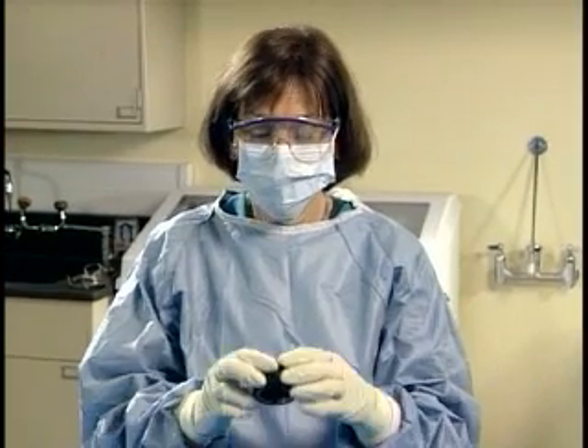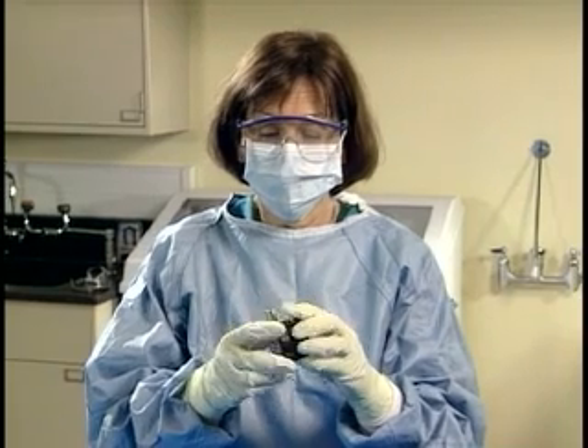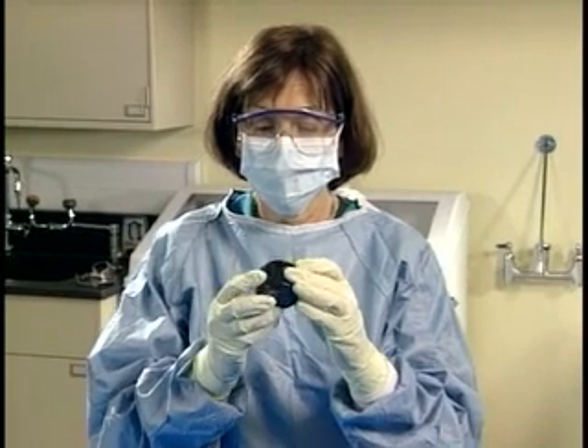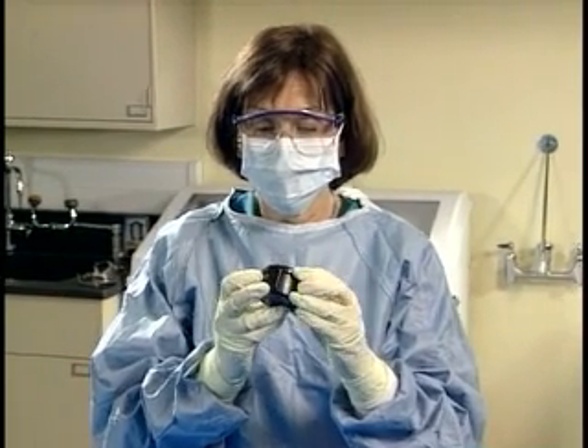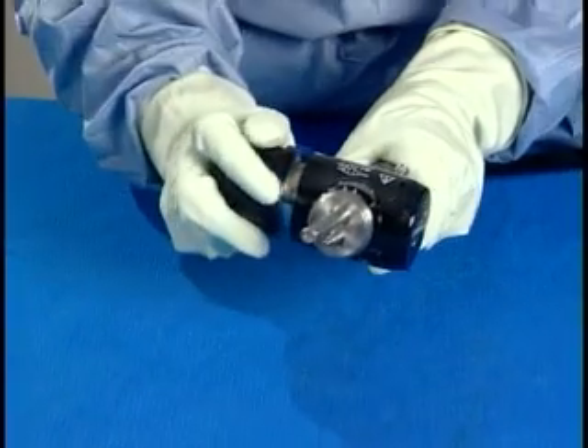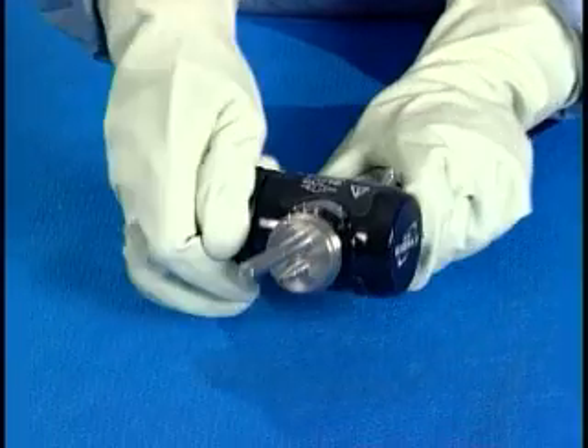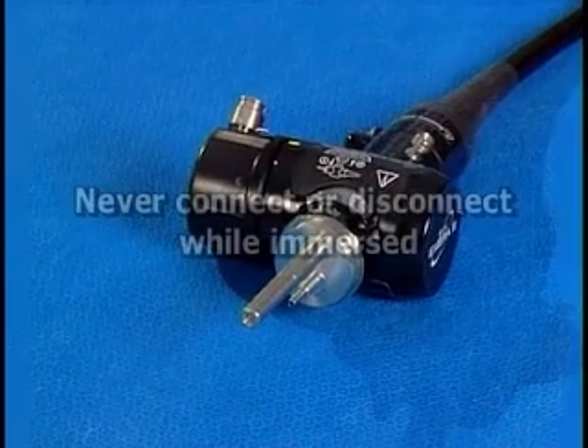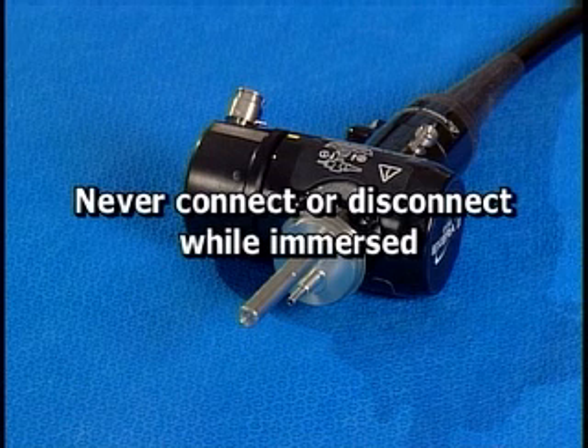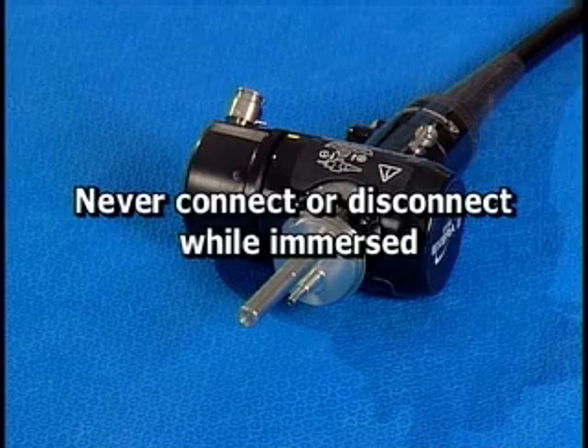Prior to immersing your endoscope in any fluid, visually inspect the water-resistant cap for damage. If it is damaged or wet, use another cap. Attach the water-resistant cap to the endoscope. Remember, never connect or disconnect the water-resistant cap while the cap or the endoscope is immersed. Doing so will damage the endoscope.